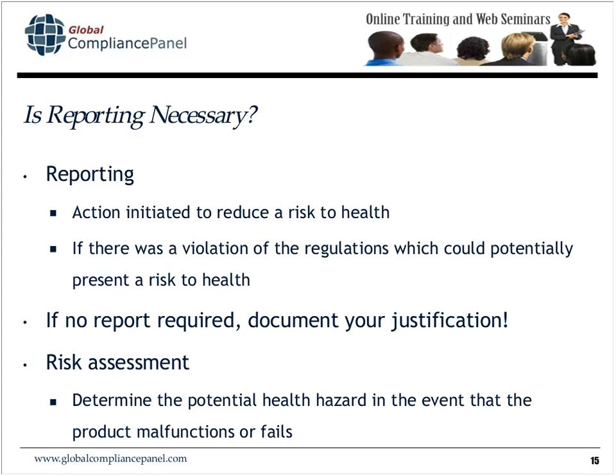And you're going to perform a risk assessment. You're going to determine the potential health hazard in the event that the product malfunctions or fails. In many cases, you can refer to the risk assessment that was done during the design process for your device. In some cases, if you have an older device or you've just recently become FDA compliant or ISO certified, you may not have performed a risk assessment yet. However, this is the time when you're going to perform a risk assessment to determine what the potential health hazard is.